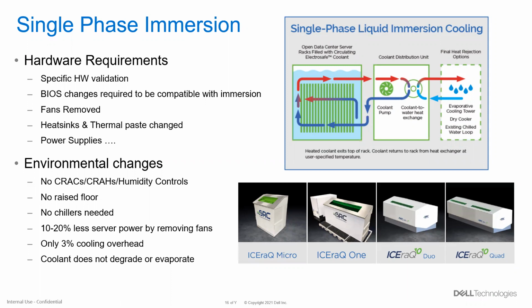The tanks have heat exchange also to facility water, but the coolant that is pumped into the tank, again, is pumped from the bottom to the top, captures heat, and extracts it back to that heat exchanger. But there's no special equipment on the gear. There are no cold plates. The fluid will basically wash over the entirety of the server components.